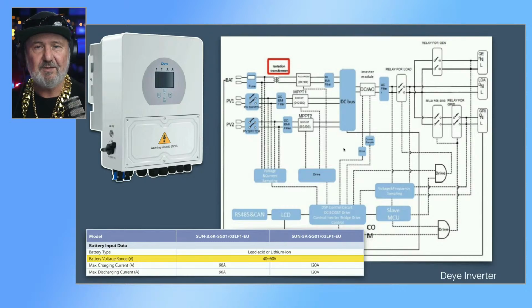There is a way of testing to see if you have galvanic isolation, but beware, you probably want to wear safety glasses and gloves when you do this. So if they claim that it's a separated inverter and you were to connect one of the battery terminals to earth, if the smoke comes out of the inverter, they were lying. If it doesn't, it's all good. Because if you don't have galvanic separation, the moment you earth one of the battery terminals, you'll create a direct bolted fault through the power conversion stages of the inverter. It'll bring AC onto the electrolytic capacitors, which are polarized, of course, and they go big time.